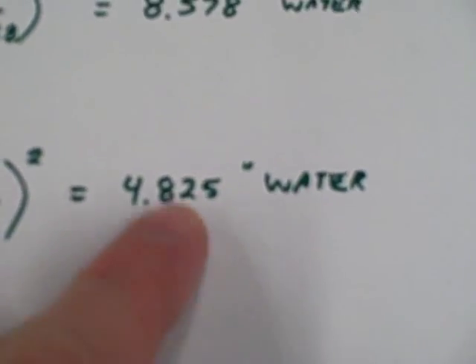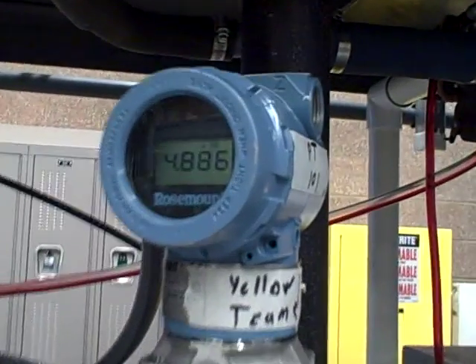We have calculated 4.825 inches of water. That's our calculated value, 4.825 predicted. And over here, 4.88, not too far off.